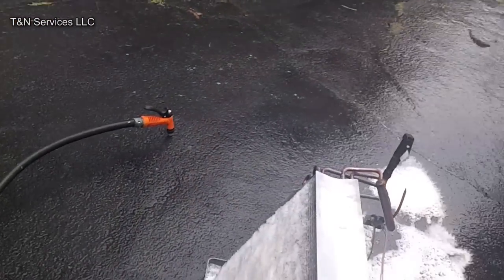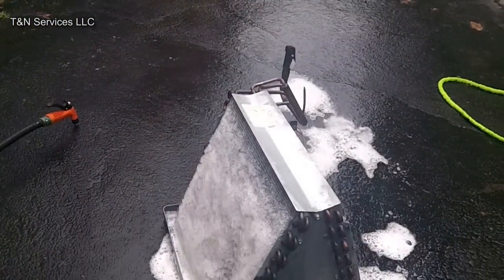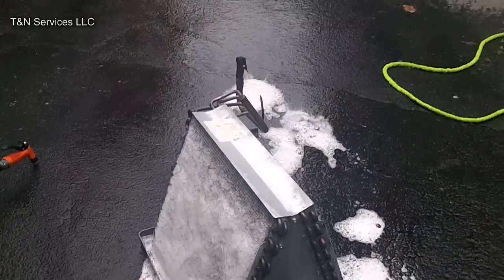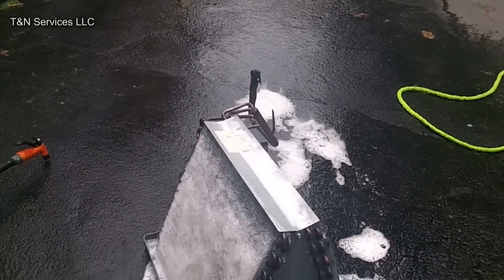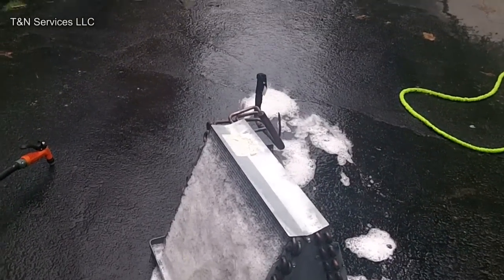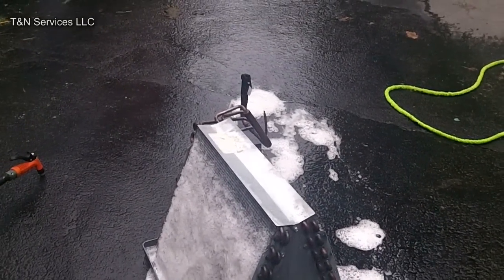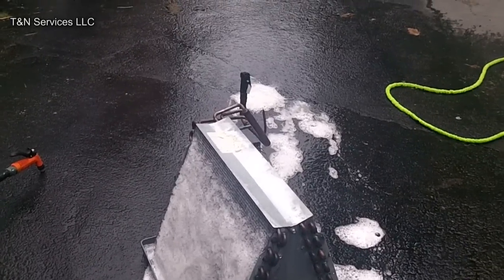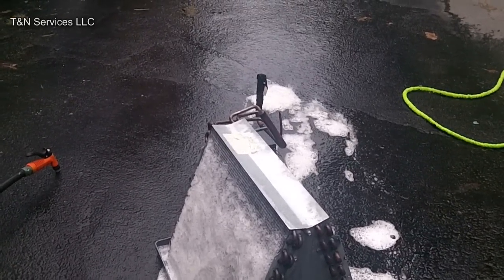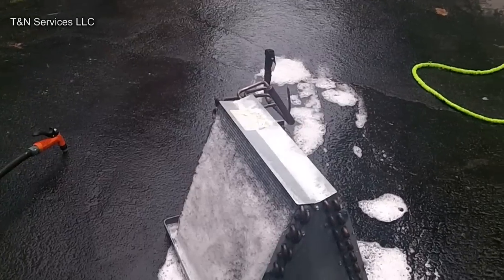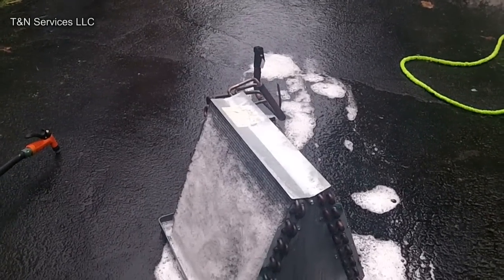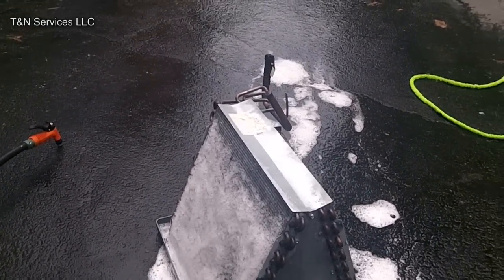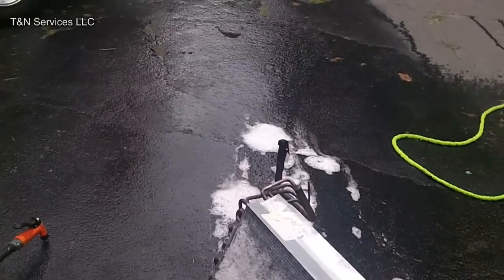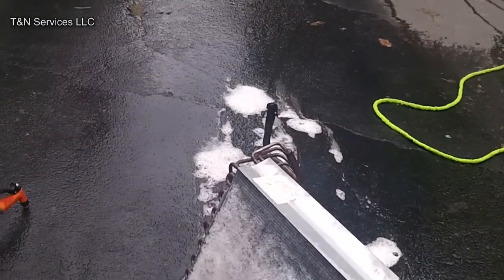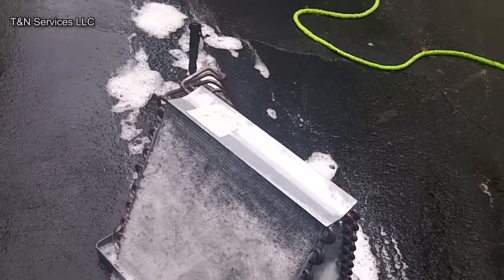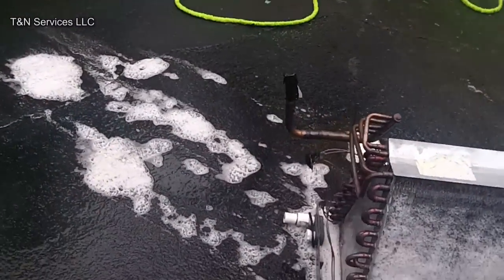She did say the last guy was here. They called him out for a water leak, and he did put a trap in it, but I'm guessing it was frozen up before and thawed out and leaked on the floor. I guess he put his gauges on it, but without checking superheat, you'll never know. You'd just say things are good, even though they're telling you it's never cooled since they've been there. I'm gonna get that sprayed out and go put it in.